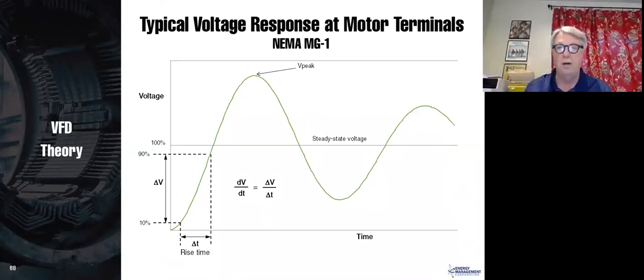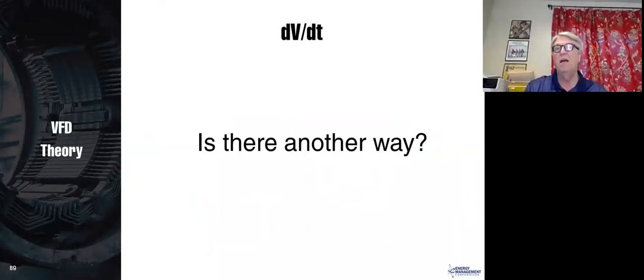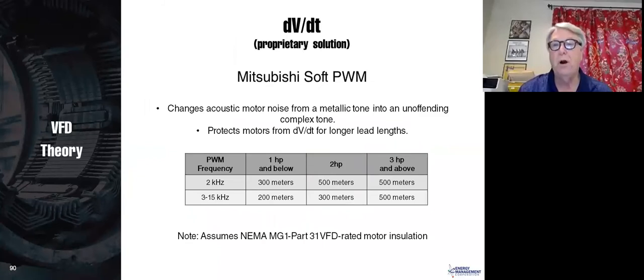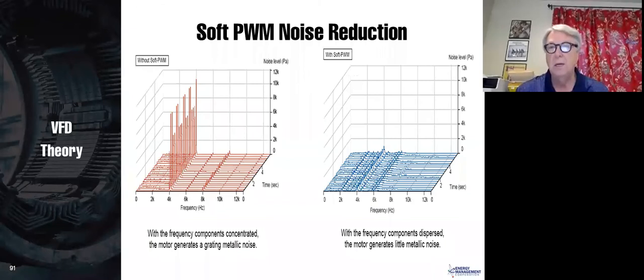This shows you how to measure your dV/dt. There are some drives that will allow you to go out to 1,600 feet, about 500 meters, without having a dV/dt filter. And if you have one of those, then that's great. You don't need a dV/dt filter. Our rule of thumb is, well, I'll tell you that in a moment.